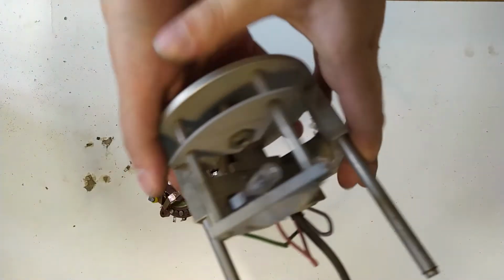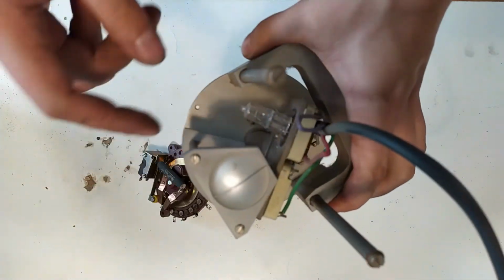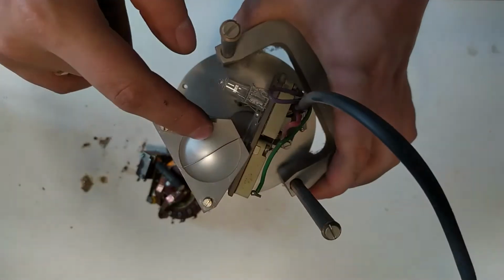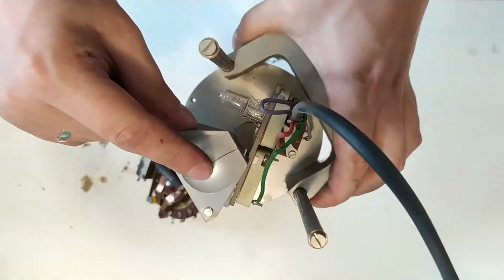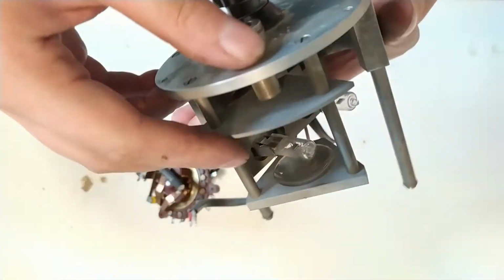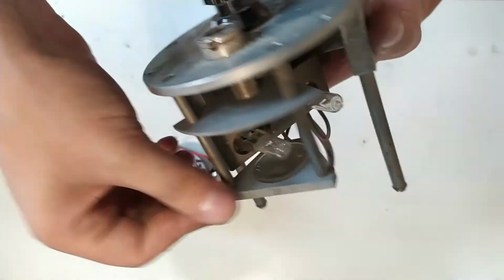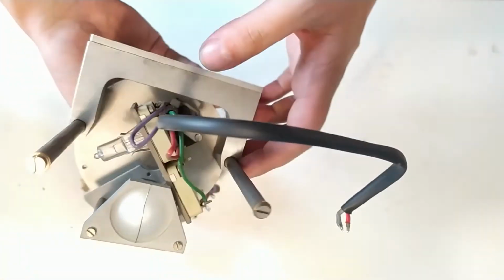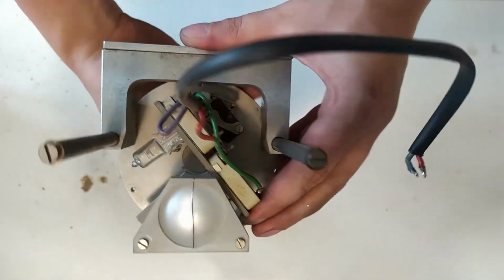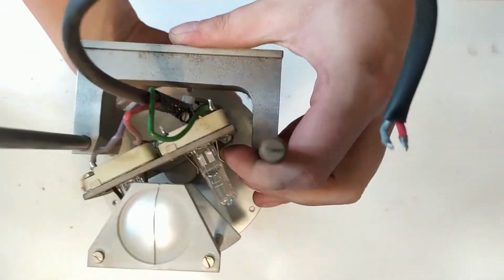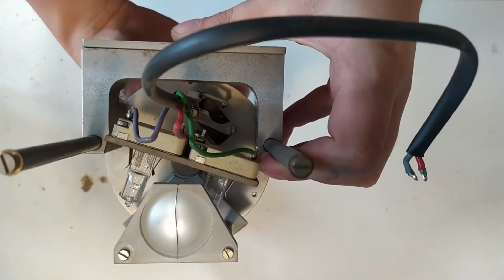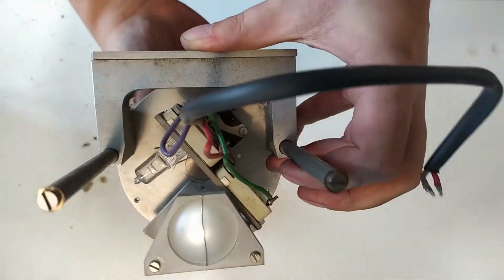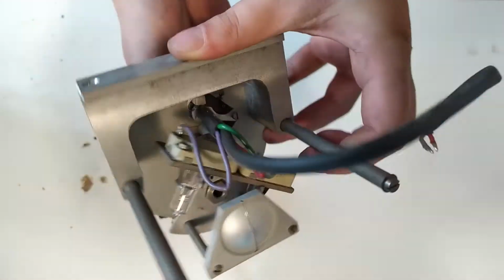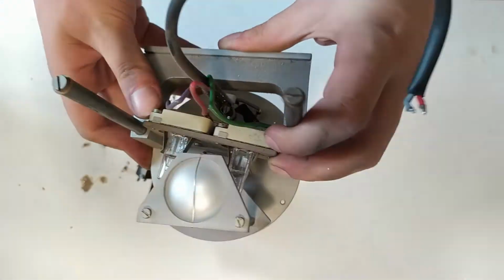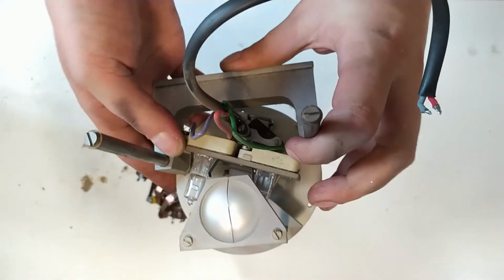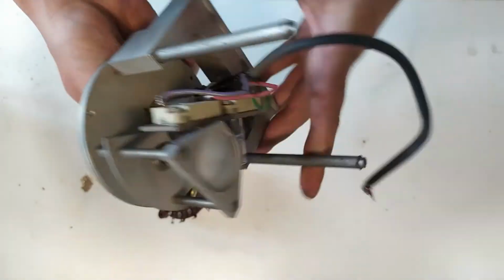This lamp holder here is kind of interesting. It's not a machined bit - it's a lens that's held in by this little wire, not integral with this sort of guide block. How it detects which lamp needs to be on is there's a little micro switch down there, and if you turn it around at this point it will switch on the other lamp like this. I don't know why there's the same two lamps in there though, but this might not be original.